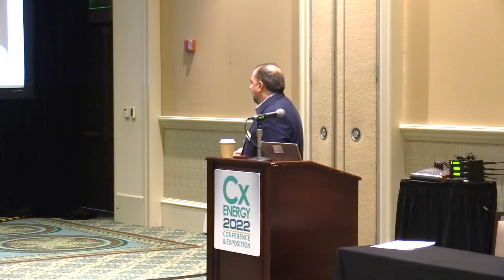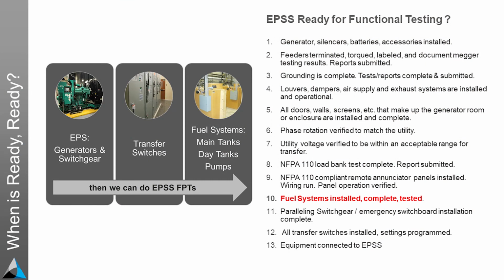Like, well, does it alarm? Well, no, but you can read what the fuel is. And, well, even if it did alarm, it doesn't matter. The code says that it has to be part of the generator's remote annunciator panel. So we're testing all that to make sure that works. And again, that's the third piece of our triad.